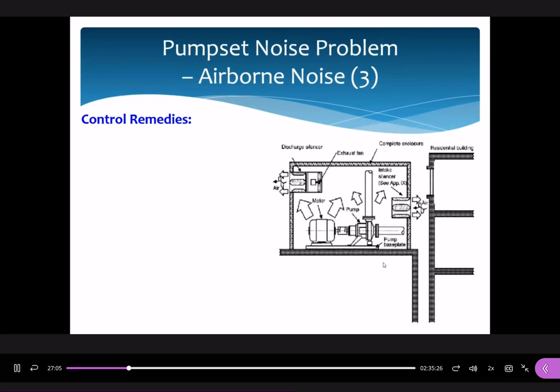We can also fabricate a complete enclosure with silencers to limit the radiation of acoustical energy. Please pay attention to these provisions - when we build fully enclosed structures to cover this equipment, like this one, because under the operation of this motor you could generate heat effects, so we need to maintain good airflow between inside and outside areas. Otherwise it may induce overheating effects inside the enclosure.